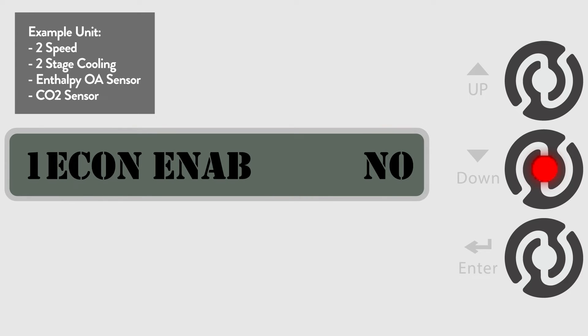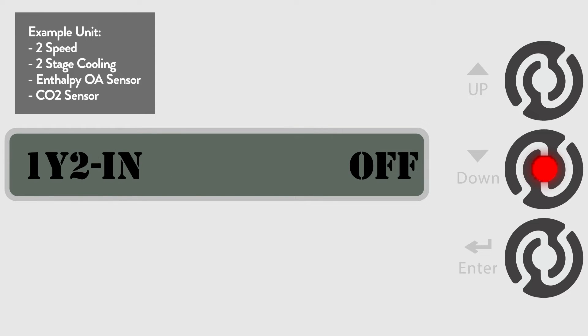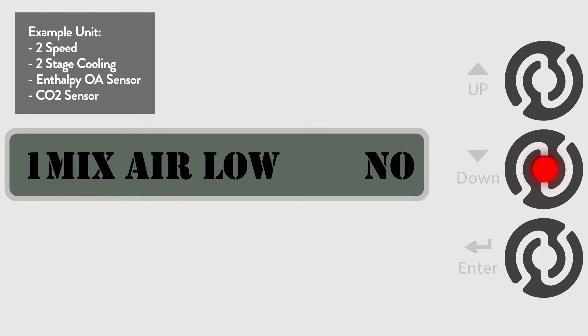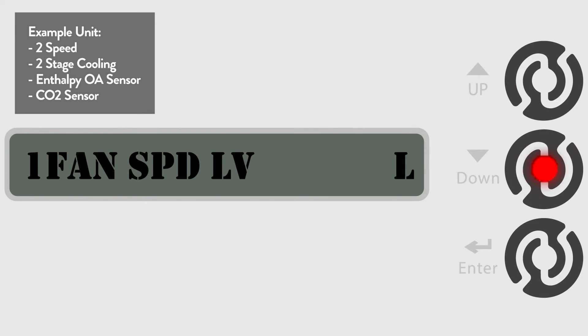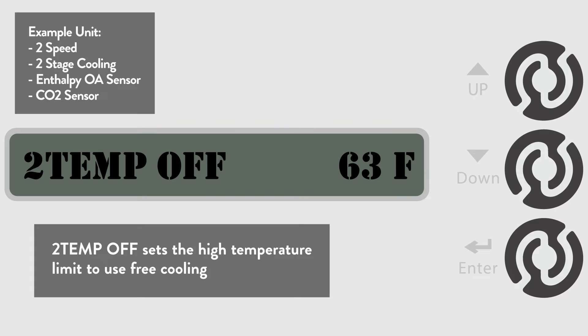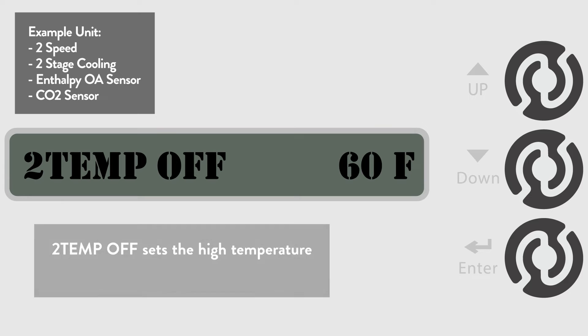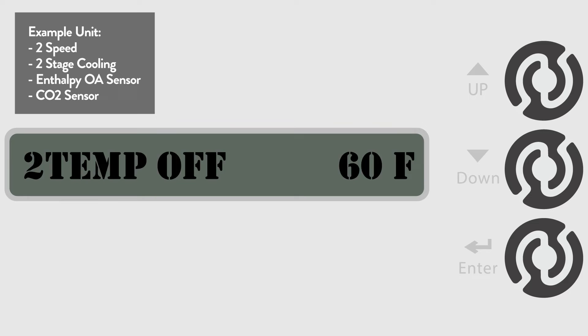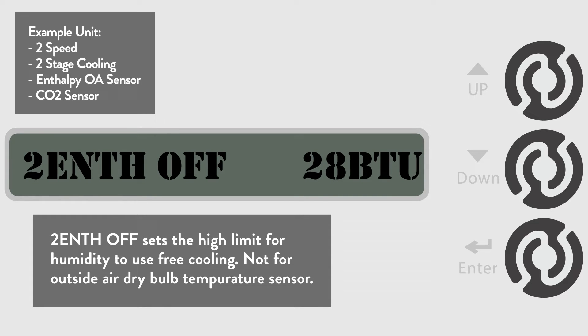We are using temperature and humidity for the outside air sensor, so first let's go to the 2TEMP off menu. This sets the high temperature limit where the economizer free cooling is locked out. The default is 63 degrees, but let's change it to 60 degrees for this example. In the 5 configuration state menu, we selected the temperature and humidity or enthalpy outside air sensor, so now we will adjust the humidity setpoint. Go to the 2ENTH off menu, which sets the outside air humidity limit where the economizer free cooling is locked out. The default is 28 BTU per pound, but we will change the setting to 25 BTU per pound.